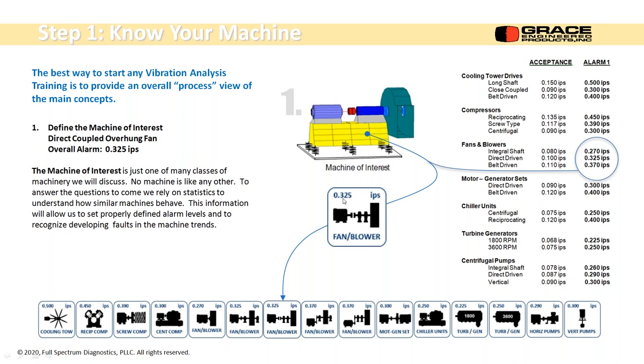It's telling me that the vibration allowable level for this machine statistically is 0.325 inches per second. So this is a velocity measurement. And we're going to talk more about velocity and displacement and acceleration in a minute. But this is the alarm level that would be set in the software system. So the machine's taking data every hour, every minute, what have you.